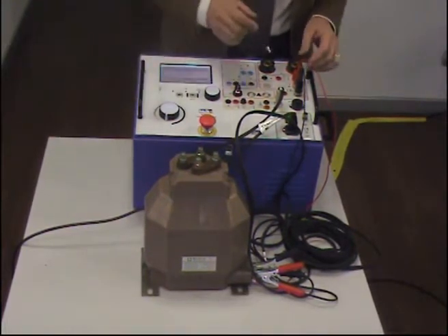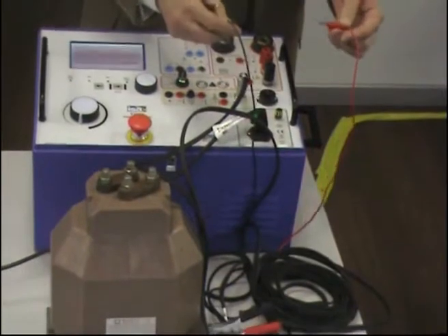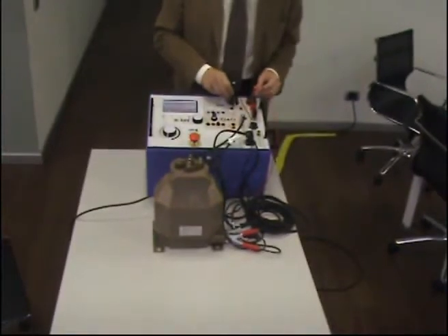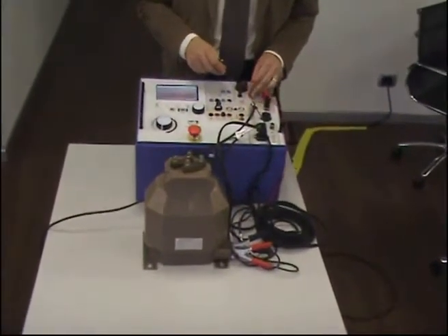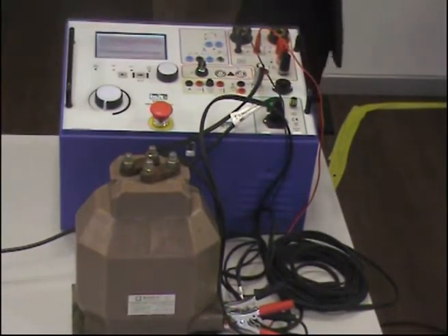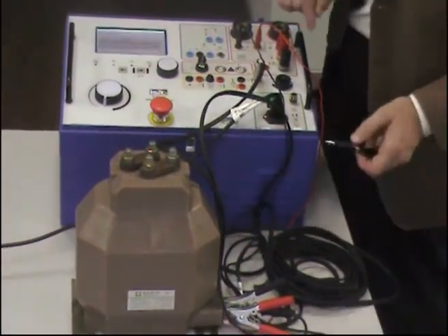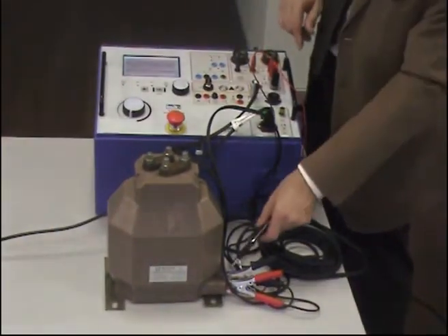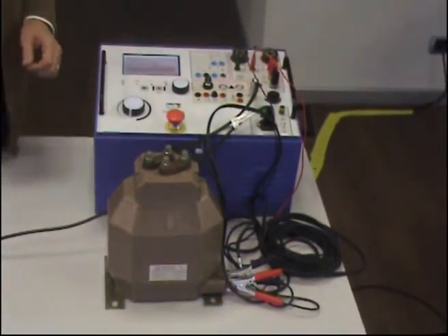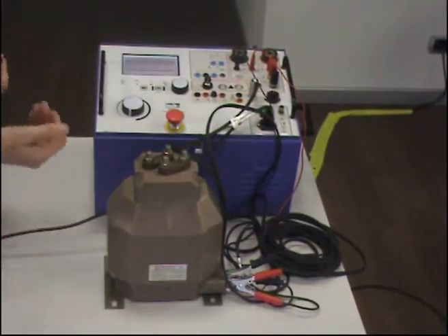Anyway, in our test, you see, this is again my secondary side of the current transformer. I remove it from where it was, and I go here to this source of DC current. Okay? Being a resistance measurement, I also need to connect my voltage measurement input to the secondary winding so that I can measure the voltage and the current that I am injecting, and by the ratio I know the resistance.